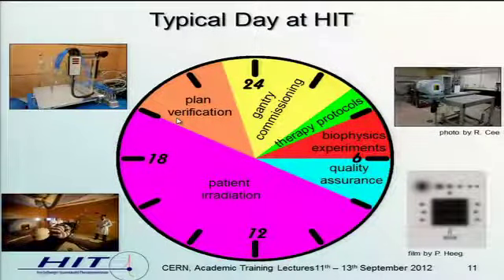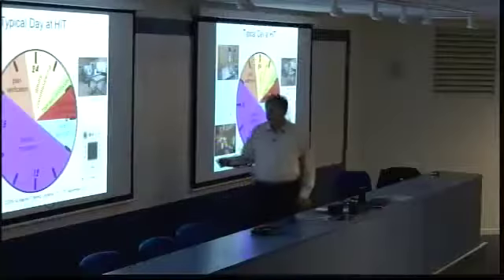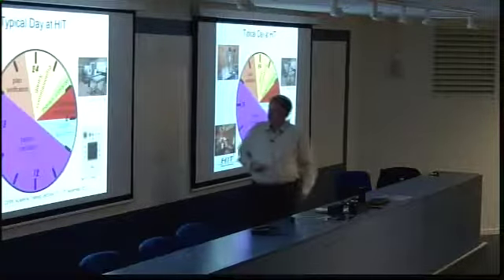Okay, this is the overall plan, and this is what a day at HIT looks like on the 24-hour clock. So let's start here at 6 o'clock. Then our medical physicist colleagues come and do 2 hours of quality assurance. They check the whole treatment and irradiation workflow, and the dose distributions. This is a typical film that they make in the morning, one at each place. This took about 2 hours for the 2 horizontal places at the moment. Then from 8 to 8 we have the patient treatment. And after that, in the evening and early night, there is a slot of 2 to 3 hours for plan verification.